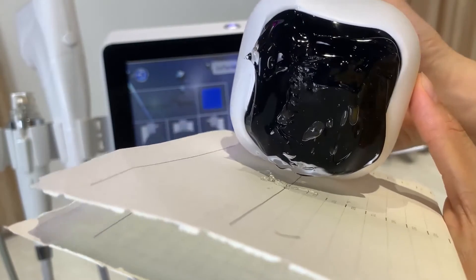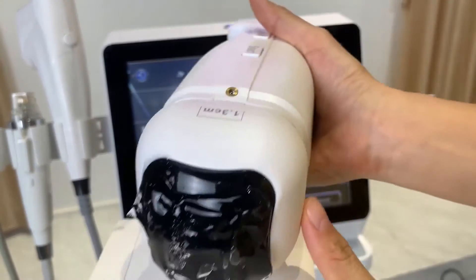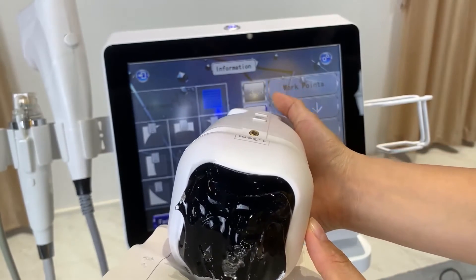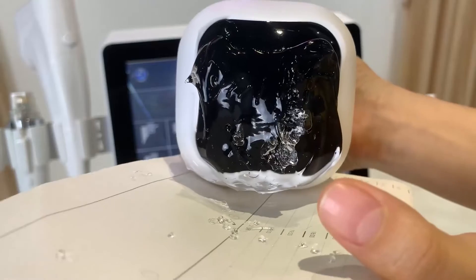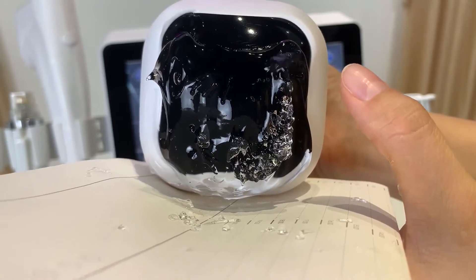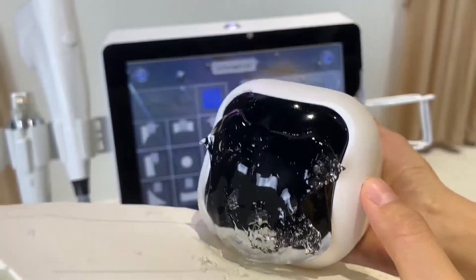The liposonic delivers energy very quickly from left to right. Anytime you want to stop, press the work button. You can then adjust the energy level higher or lower and continue treatment by pressing the work button again. The screen displays how many shots remain. The energy distribution is very even from left to right and top to bottom, and the energy for each dot is precise and consistent.